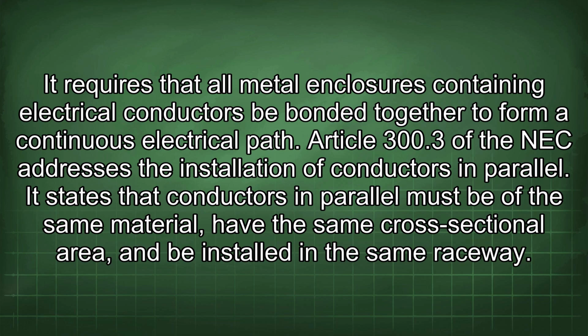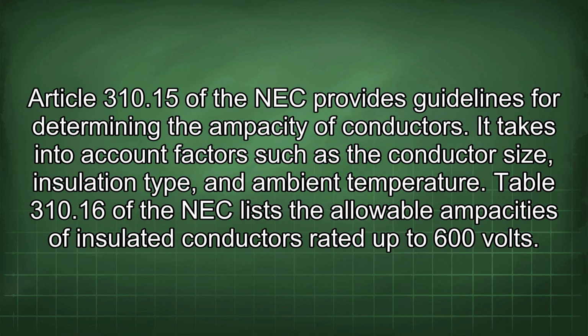Article 300.3 of the NEC addresses the installation of conductors in parallel. It states that conductors in parallel must be of the same material, have the same cross-sectional area, and be installed in the same raceway. Article 310.15 of the NEC provides guidelines for determining the ampacity of conductors. It takes into account factors such as the conductor size, insulation type, and ambient temperature. Table 310.16 of the NEC lists the allowable ampacities of insulated conductors rated up to 600 volts.